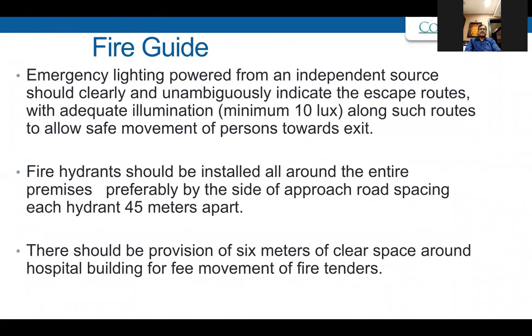Next, please. So emergency lighting is also compulsory in these fire staircases. Fire hydrants, all of you are aware. And also you need to have 6 meters of clear space around the hospital building for free movement of fire tenders. In fact, nowadays for new construction, the fire department doesn't give permission if the adjoining areas are very, very congested and there is no space for them to enter from outside. So they need either space inside the hospital complex of 6 meters or immediately outside the hospital, 6 meters clear space. Next, please.